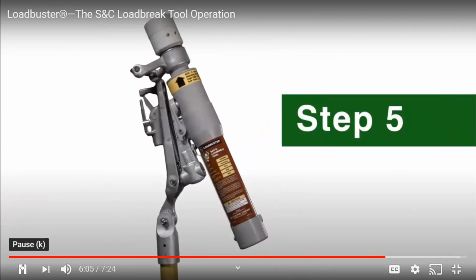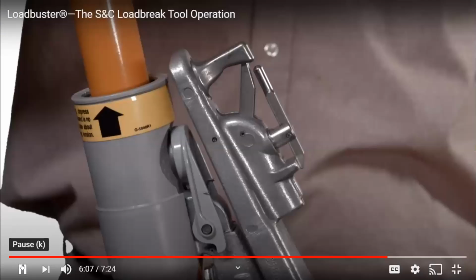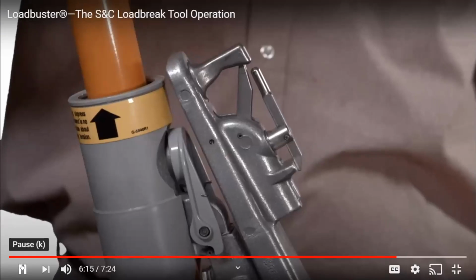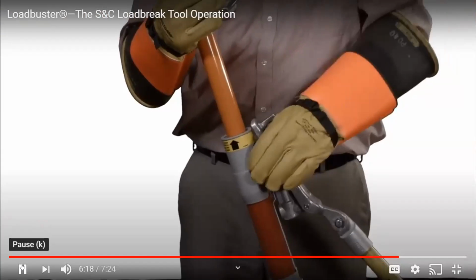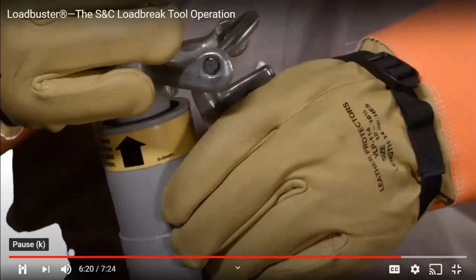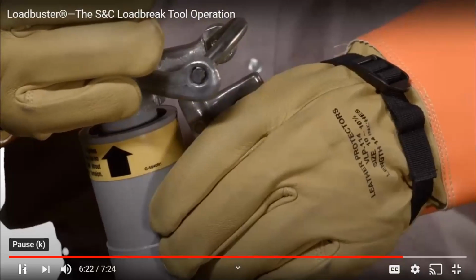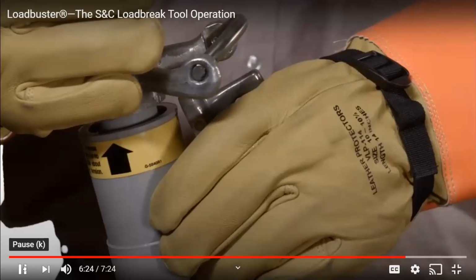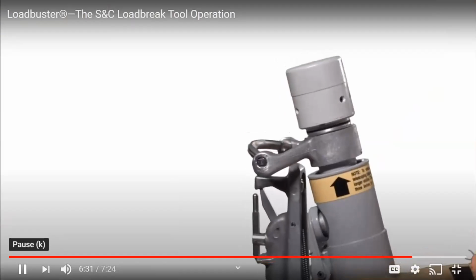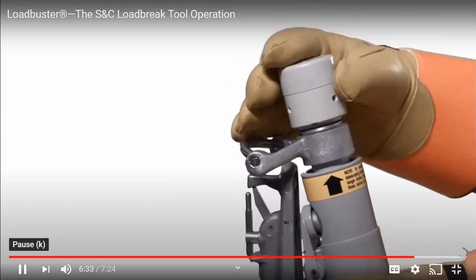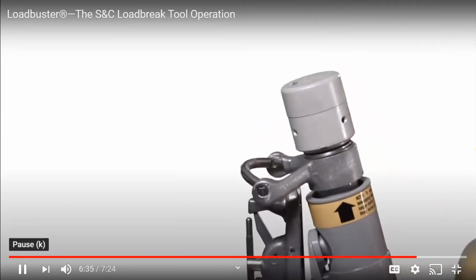Step 5. To reset the loadbuster tool for the next operation, extend the tool slightly and lift the resetting latch with your thumb. With the latch up, press down on the inner tube assembly until the tool is closed completely so the trigger can reset itself. When reset properly, the orange paint on the inner tube assembly will no longer be visible. Check for proper resetting by extending the tool about 3 inches. An increasing spring resistance should be felt.